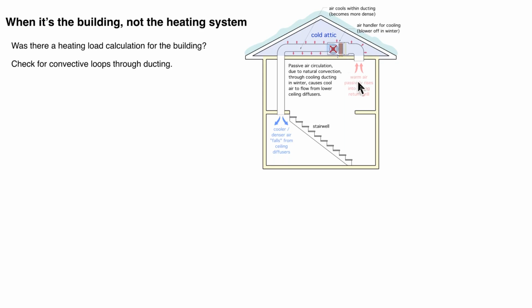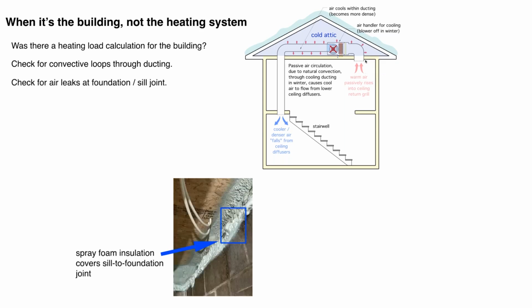And what was happening is warm air, just due to its buoyancy, would go up into this ducting in the winter. It would lose heat through the air handler, through the ducting. It would become more dense, and then it would fall and actually come out of these ceiling outlets on the first floor. You could actually put your hand up there and feel this cool air, knowing that the blower wasn't operating. So we had what was called a convective loop going on. And it's just something to be aware of. Maybe you're going to need to put something over that return air in the winter time, or put a damper system in, something that's going to block that path, okay?